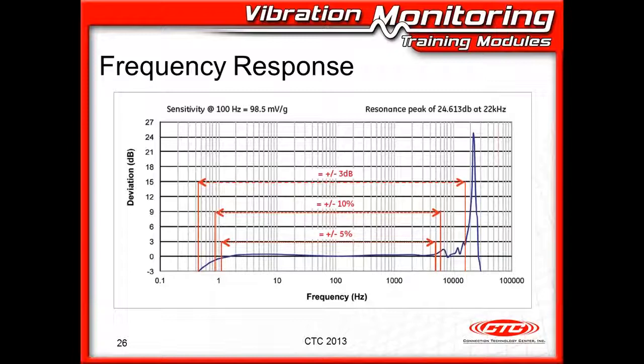So typically, when we're working in the field, when we're purchasing accelerometers, we use the plus or minus 3 dB range, and we try to work within that. And because we're running a program that usually counts on us trending our data, we're not worried about these minor inconsistencies with the amplitude, because in the trend it's always being accounted for. If you're launching the space shuttle, you need to be very nervous about things like this, but we're generally not doing that. So since we're using the trend to drive our condition monitoring program and we're relying on that trend, you're really looking for a change of something to double or 2.5 times in amplitude, and then you need to be very concerned.